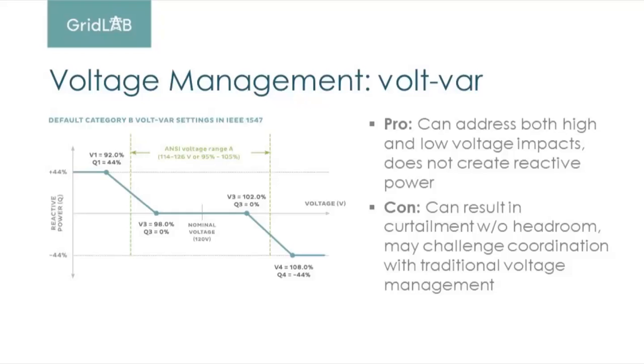The pros here are that it can respond to the voltage that's happening on the circuit, and it can deal with either high or low voltages. The negative, though, is that if the inverter doesn't have headroom and it's putting out maximum power, it may end up having to curtail if it's also being asked to put out a lot of reactive power. There's also been some concern by utilities and others that this may impact traditional voltage management, either other volt-var controls or traditional voltage devices. So there's been some concern that having your DERs try to do voltage control might confuse your traditional voltage management.